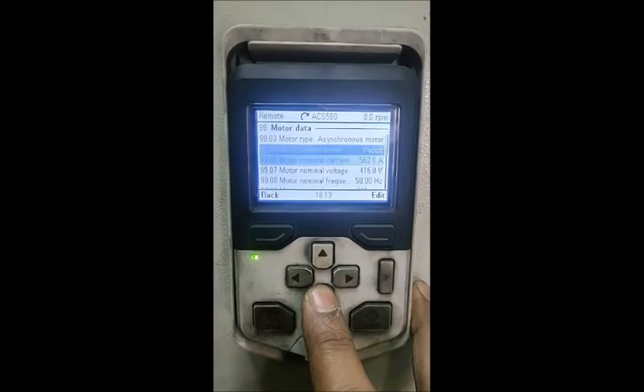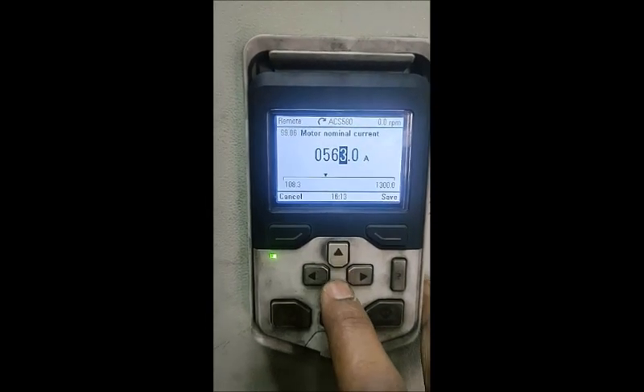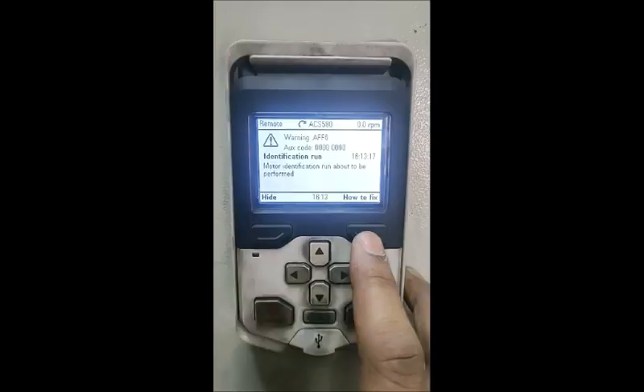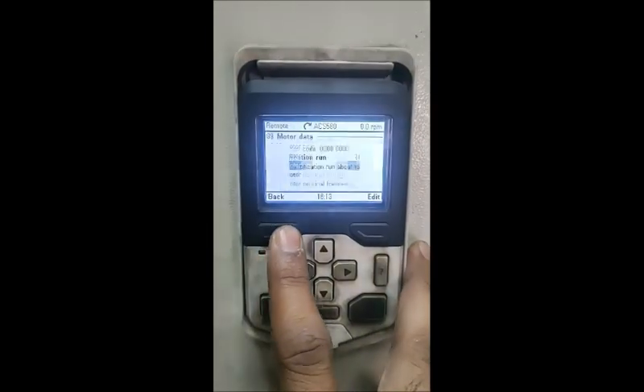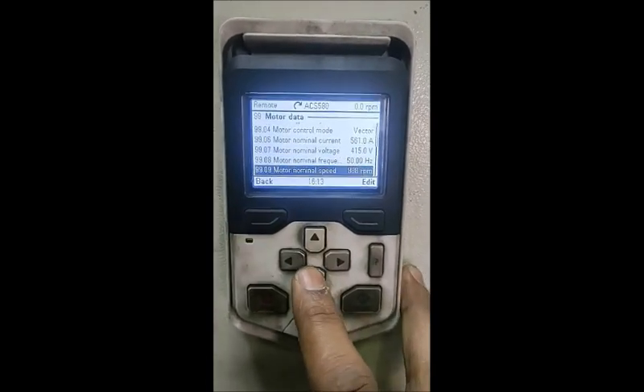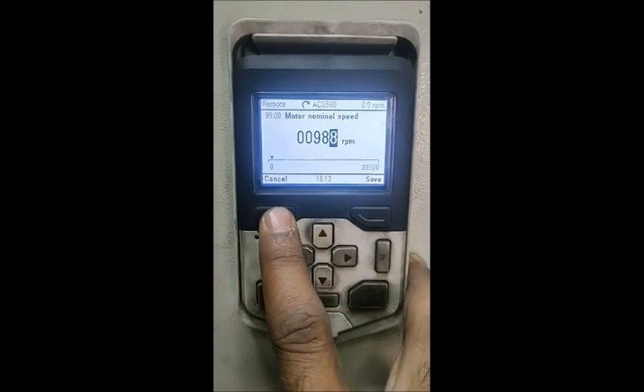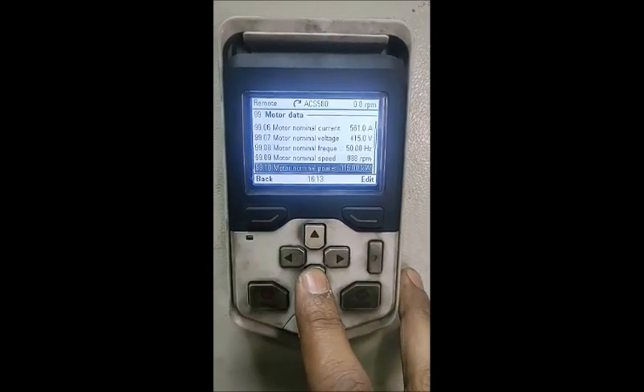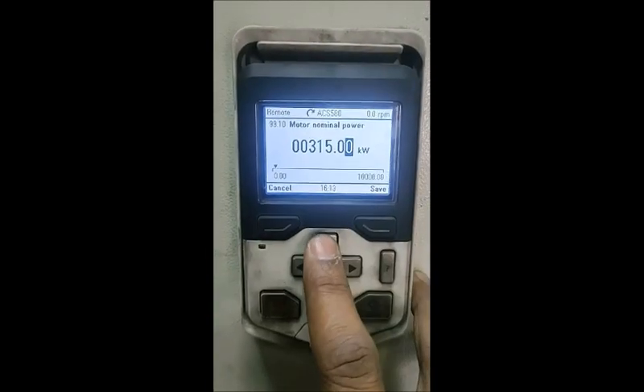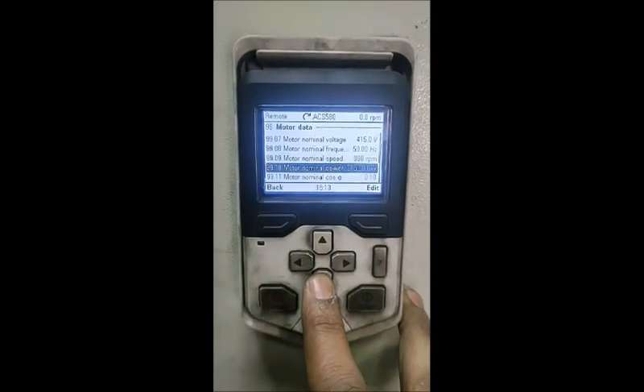Next is motor current. We can change it here using those buttons. For example, it was 62 — I have changed it to 61 and saved it. We need to save it. Once the ID run is started, you will get a warning-type notification — just dismiss it. Here we can fill the nominal speed; this is a slow speed motor, and it can also be changed up or down. Next, this is the motor rated power, which is 350 — this can also be changed. We can save or cancel as per the requirement.